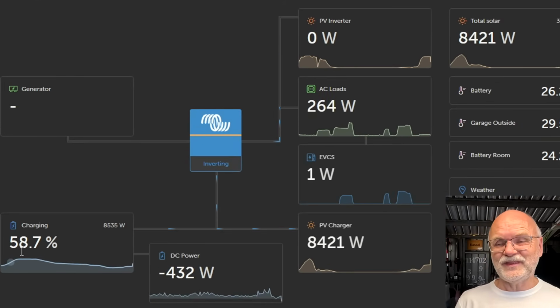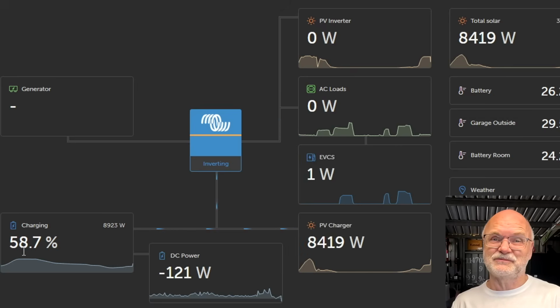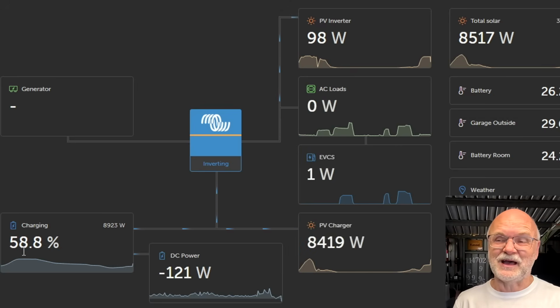So we are at 59% state of charge plus 13%, which were missing yesterday, which the Smart Shunt doesn't know about. There's nothing wrong with the Smart Shunt. We would potentially be a lot closer to the actual state of charge of the battery, but because I reset the Smart Shunt to 0% when all 3 batteries were at 2.5 volts with one of their cells and the battery shelf had turned off, I zeroed everything out and started from there with the Smart Shunt and with all 3 BMS to see what is going on when they recharge.